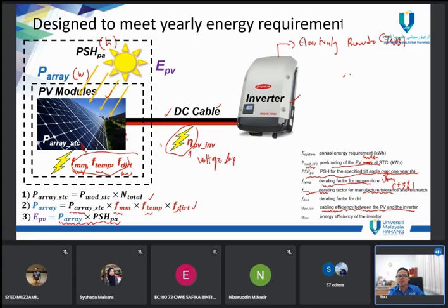When we reflect to the voltage drop, it applies MS1837:2018, where the maximum allowable voltage drop is 3%, maximum only. Max 3%. The old 2010 Malaysian standard is 5%, but we don't use that anymore. Now it is decreased to 3%, which is more optimal. Okay, so then we have that.